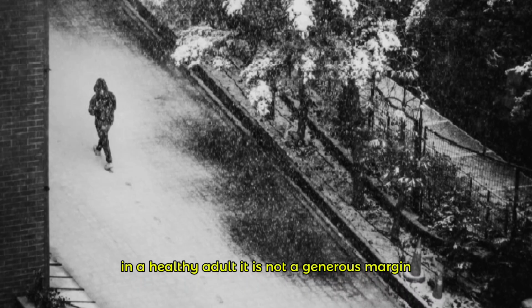It is not a generous margin. It is based on field measurements and incident data. In wet soil, conductive clay, or standing water, the ground current spreads further and the lethal radius extends. If the 60-foot figure was adopted as public guidance because any defined number is better than none, and the utilities settled on the value that covered most conditions without being so large that it lost credibility, then in the conditions it does not cover, it is not enough.